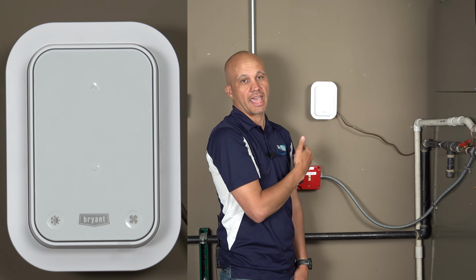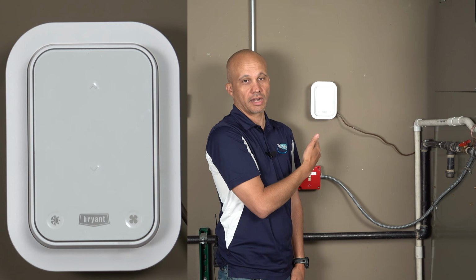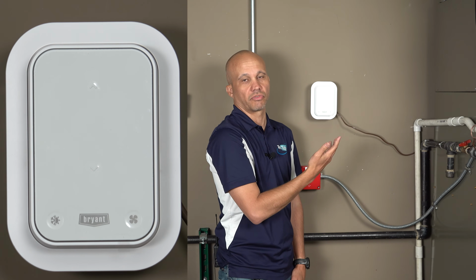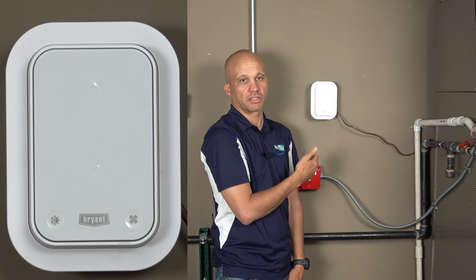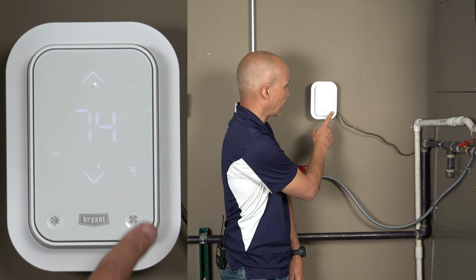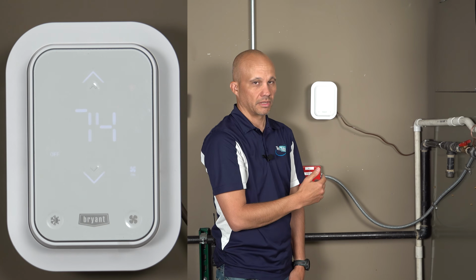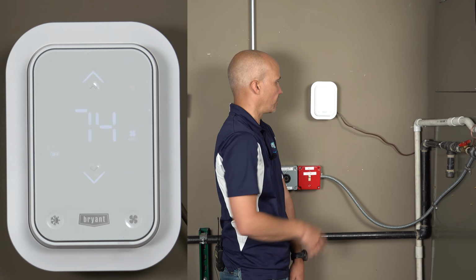So for example, if you had 18 minutes of heating this hour and you have this button on, you're supposed to get 20, it knows that it owes you 2 more minutes of running the fan. So it'll run the fan for 2 minutes extra. And then the last one, if you toggle it, is to on, where it just runs straight on, fan continuous all the time. All right, let's dive into the thermostat over here.